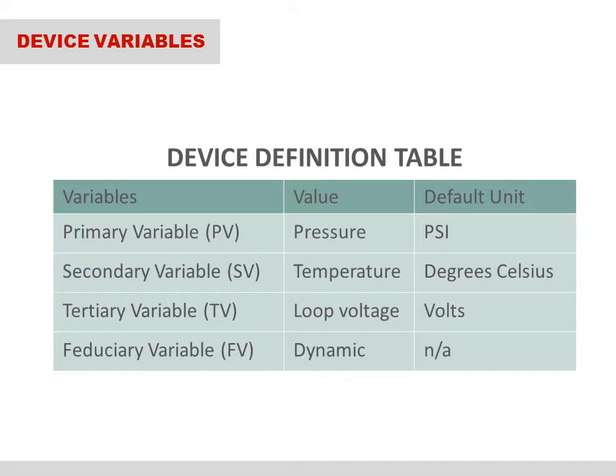Lastly, the fiduciary variable, or FV, is a dynamic or open value. It can be configured by the user to output or provide any available HART value and the desired unit of measure. Like the secondary variable and the tertiary variable, the fiduciary variable is provided via the HART digital communication protocol.